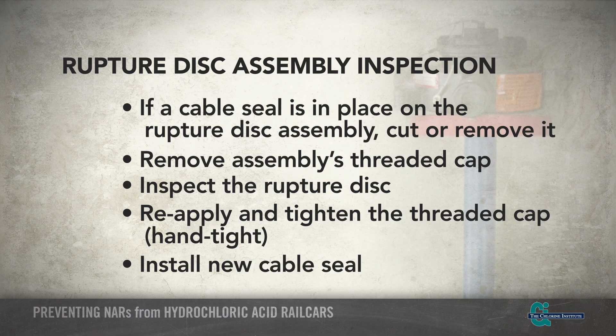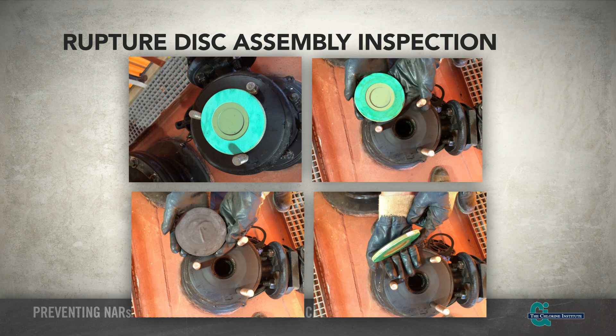Throughout the inspection process, look for cracks, signs of excessive wear, corrosion, missing components, and other evidence of altered condition of the device. A damaged or corroded rupture disc should be replaced with a new disc, which can be obtained from your supplier. Different style rupture disc assemblies may require different inspection and assembly steps.